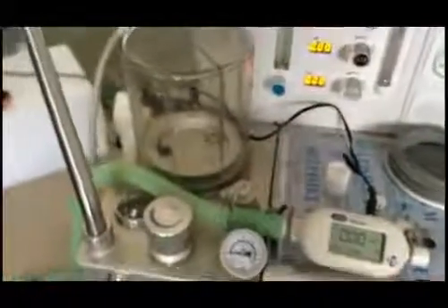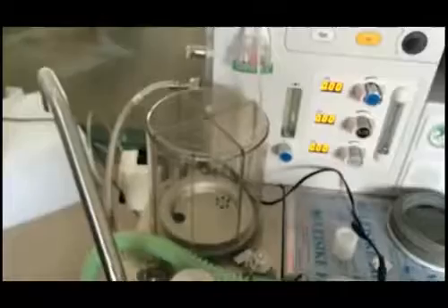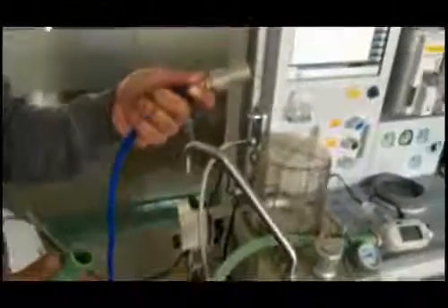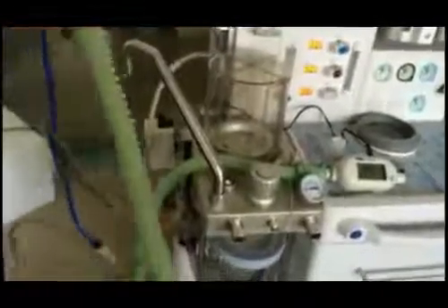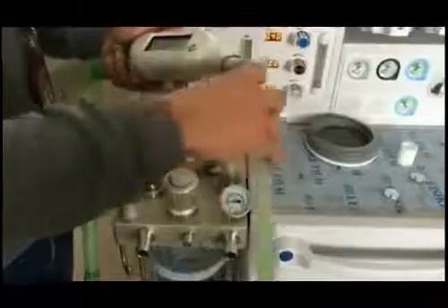The next step is to put the supply through the throttle valve, the flow monitor, and connect to the expiration port. This is the supply. This is the throttle valve. This connection will be made to the flow meter. Use a tube, connect it to the connector. Now we will connect a tube from one end of the flow meter, like this, to the expiration port. This is the expiration port.